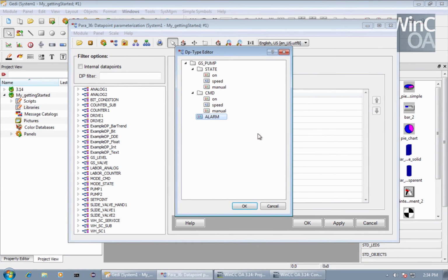Now, the thing about object-oriented platforms is you put in upfront engineering time to create a template. In this case, we're building a pump template. The powerful nature of object-oriented programming is that I can build in all of my configurations into an object like this pump. And this template can be instantiated, meaning that I can build children off of this parent template. And if I have mass engineering or repeatability in my applications, it makes the most sense in the world to use an object-oriented platform because it makes everything so much easier.